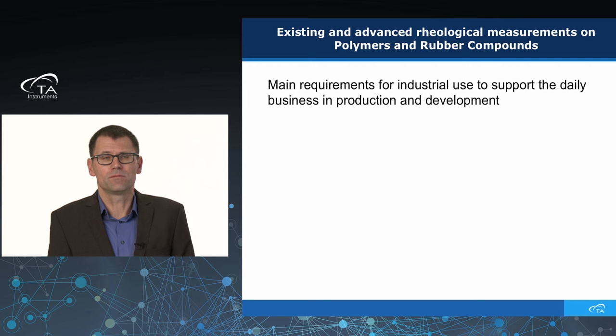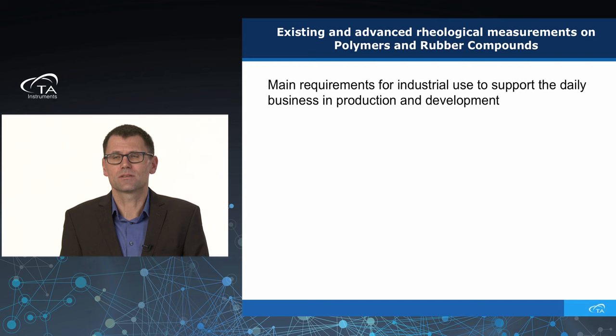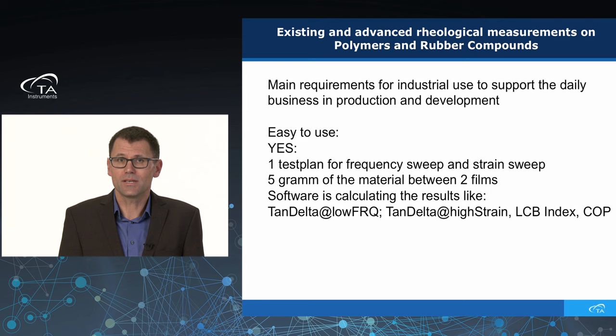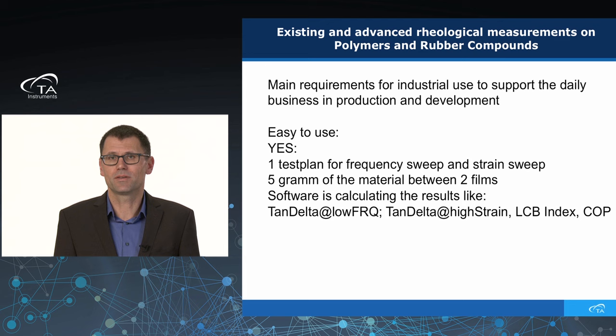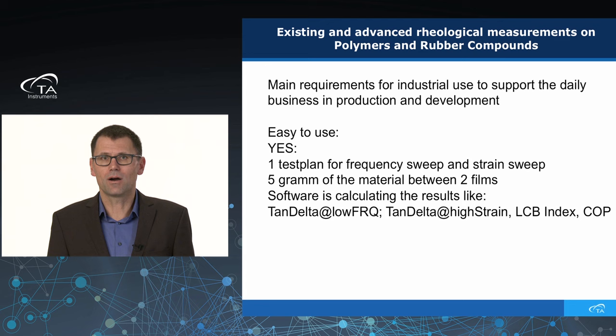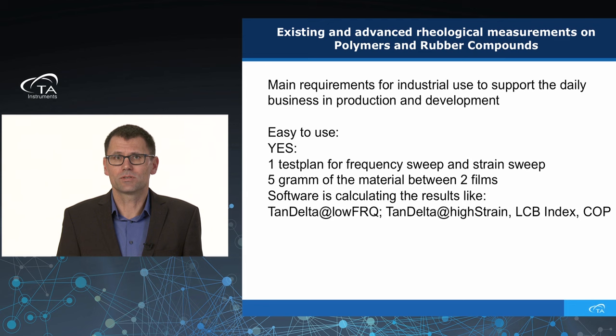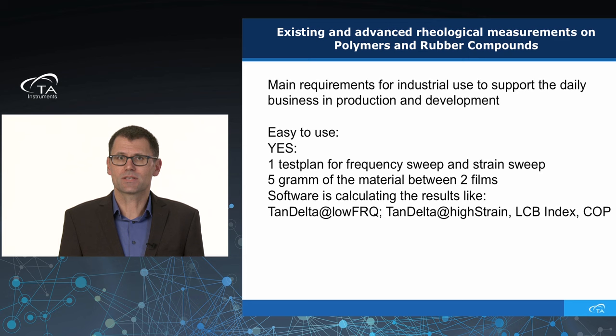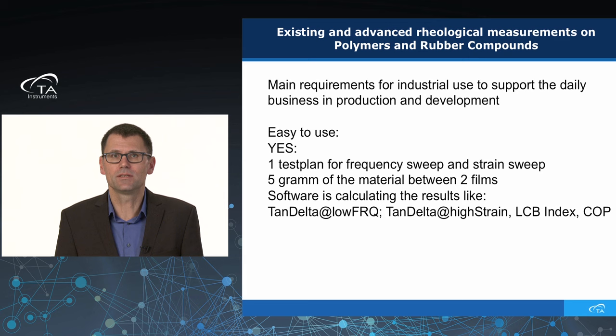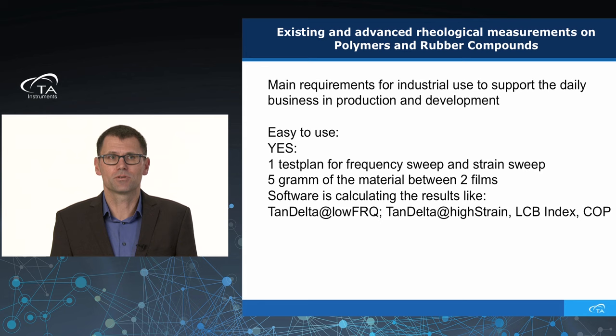A key requirement when introducing this in industry is that it must be easy to use in daily business. The answer is yes — it is one test combining a frequency sweep and a strain sweep, taking about 10 minutes. It is not a half-hour or two-hour test. The operator does exactly the same as with the MDR: take five grams, place it between two films, put it in the instrument, and the software calculates all necessary values to characterize polymers and compounds in a very thorough way.